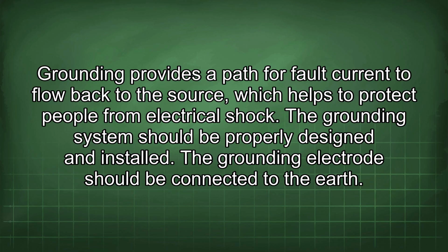Grounding provides a path for fault current to flow back to the source, which helps to protect people from electrical shock. The grounding system should be properly designed and installed. The grounding electrode should be connected to the earth.